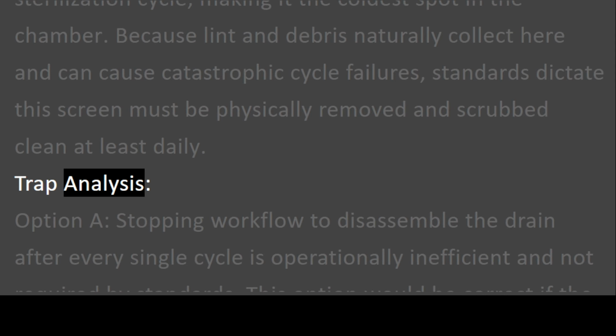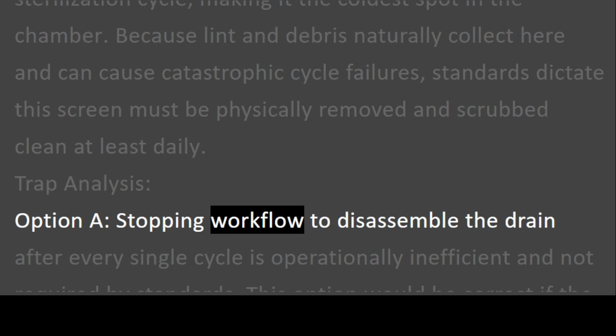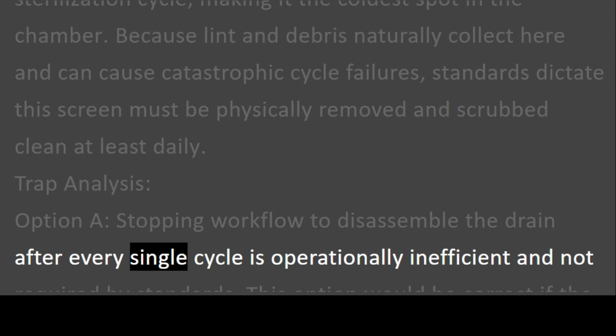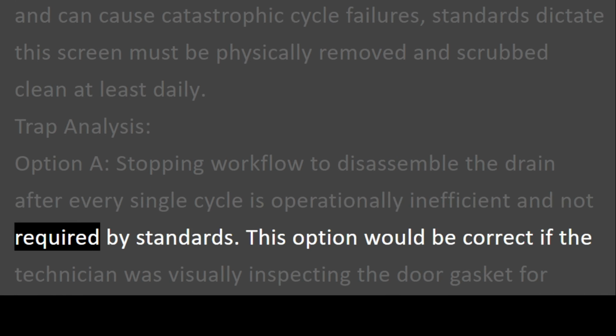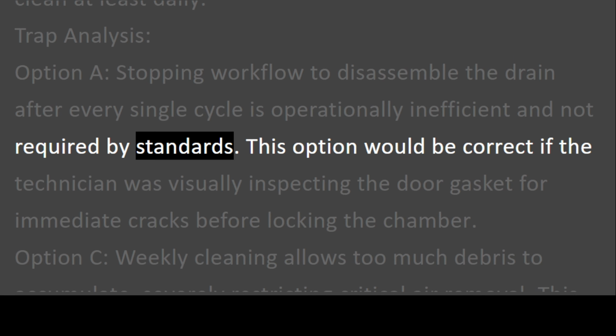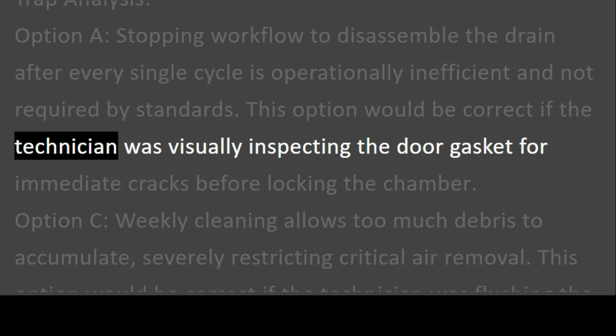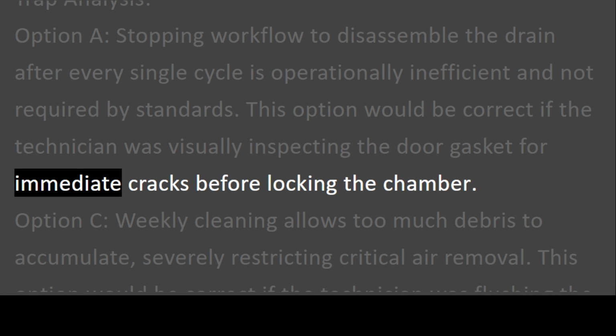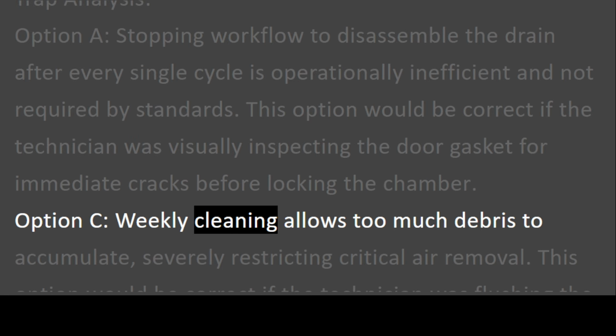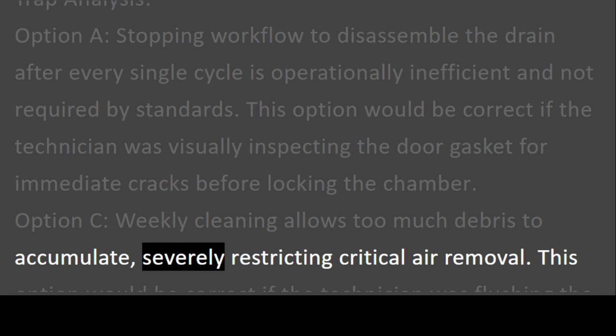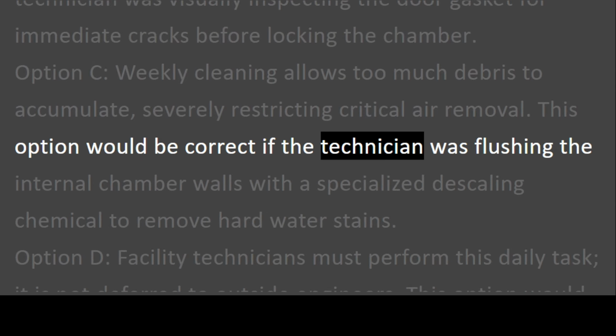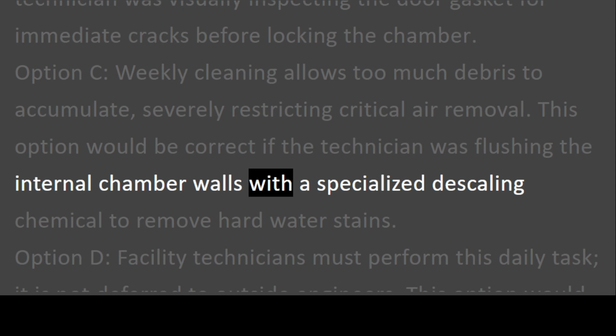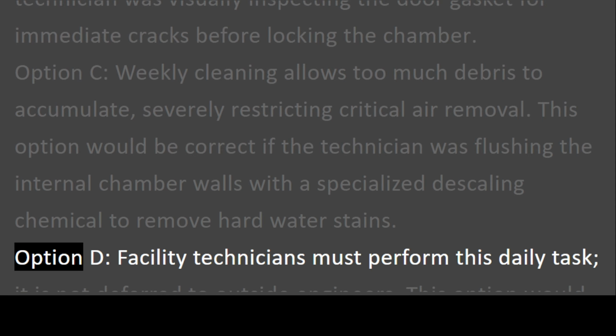Trap analysis. Option A. Stopping workflow to disassemble the drain after every single cycle is operationally inefficient and not required by standards. This option would be correct if the technician was visually inspecting the door gasket for immediate cracks before locking the chamber. Option C. Weekly cleaning allows too much debris to accumulate, severely restricting critical air removal. This option would be correct if the technician was flushing the internal chamber walls with a specialized descaling chemical to remove hard water stains.